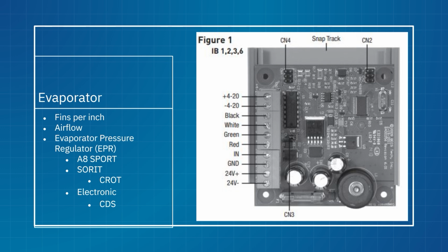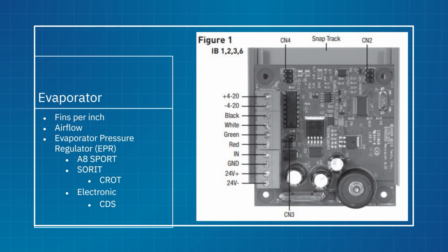Now, if you notice, of all of my wiring on here, in order to control an EPR, I've got to have an input. I've got to have pressure, if I'm going to control it like a regular EPR, or temperature, and we'll talk about the difference between those two control strategies in a minute. And if you notice, this board has neither. It has no input as far as pressure or temperature. What it has for an input instead is a 0 to 10 volt DC signal or a 4 to 20 milliamp signal. That's it. Which means something else is telling it how far to open, and it's just opening the valve that far.